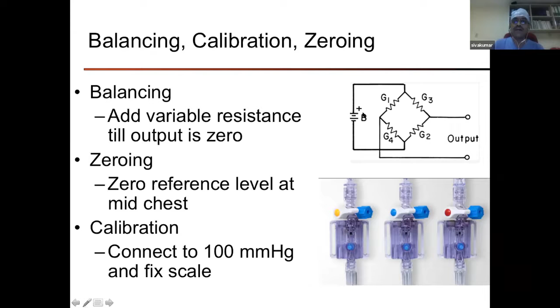And when the resistance is changed, the input voltage and the output voltage will be different. Now come three terminologies: what is balancing, what is zeroing, what is calibration. Whenever a transducer is exposed to no cardiac chamber, what should actually be our output? Output should be zero. If the output is zero, then the pressure recorded by the pressure transducer will show as 0 millimeters of mercury. And that is what we want.